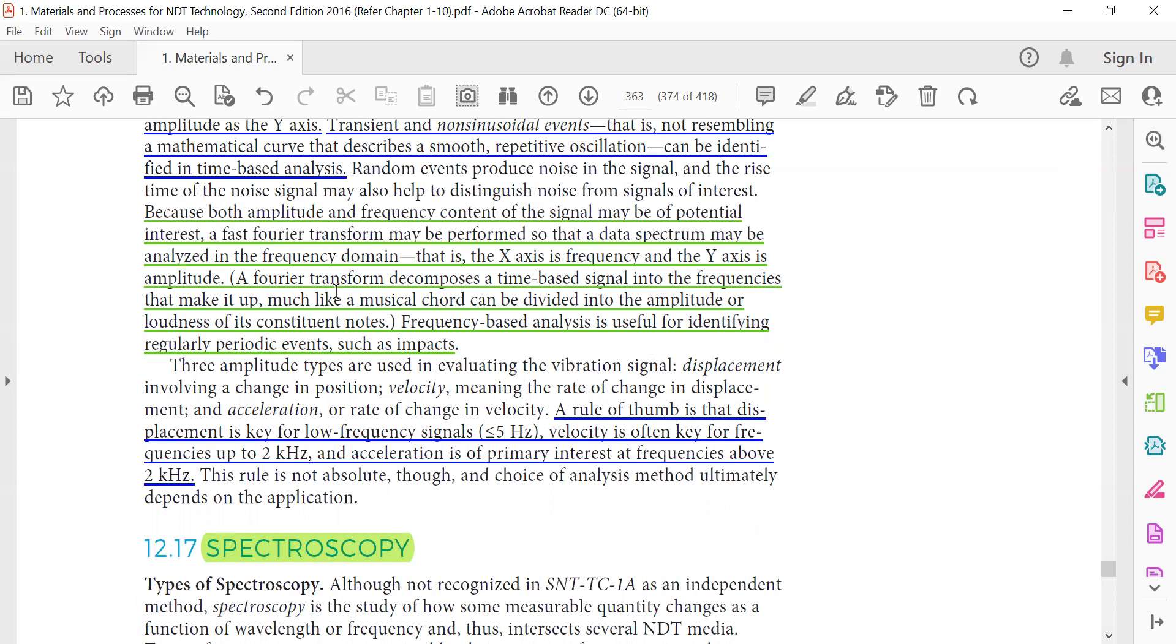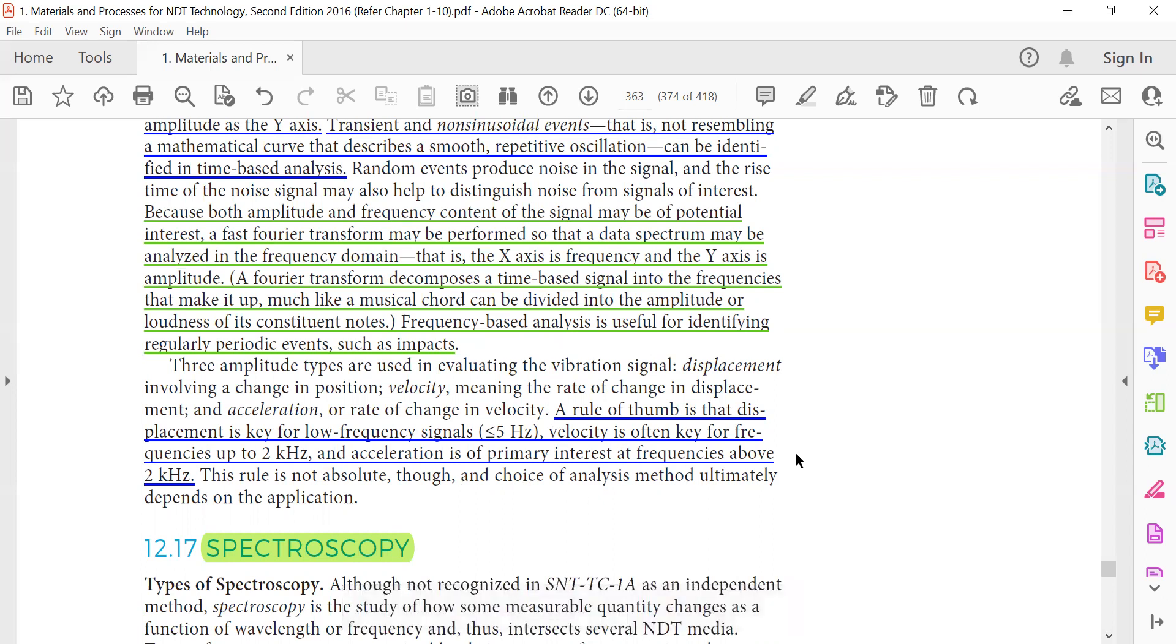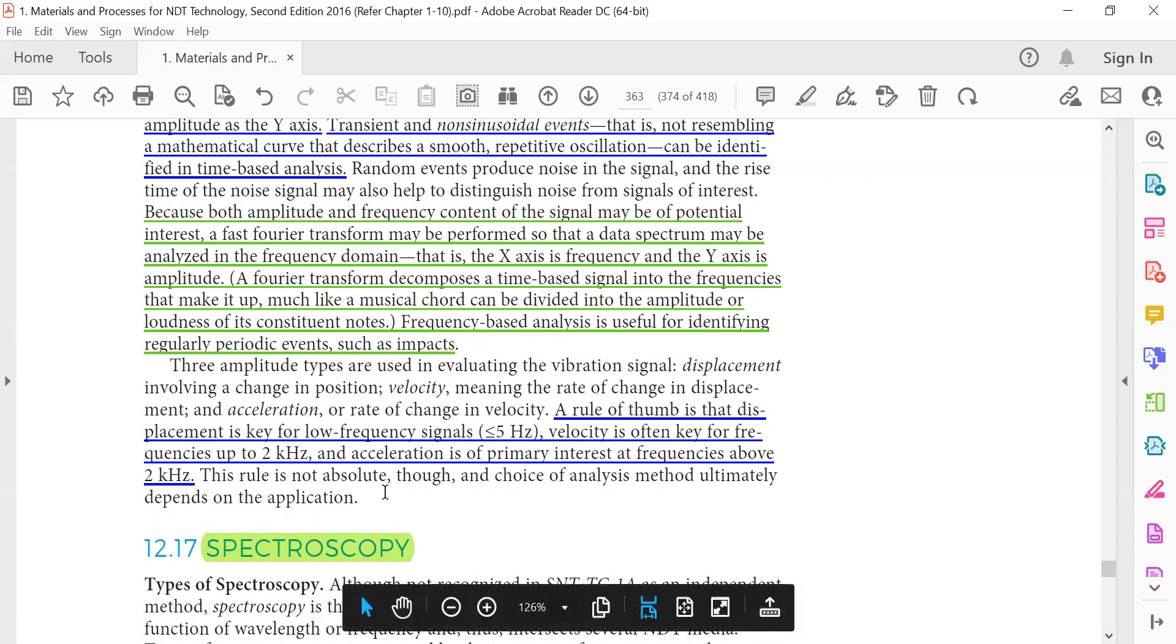Much like a musical chord can be divided into amplitude or loudness of its constituent notes, frequency-based analysis is useful for identifying regular periodic events such as impacts. The rule of thumb is that displacement is the key for low frequency signals less than or equal to 5 hertz. Velocity is the key for frequencies up to 2 kilohertz, and acceleration is the primary interest at frequencies above 2 kilohertz. This rule is not absolute though, and the choice of analysis method ultimately depends on the application.